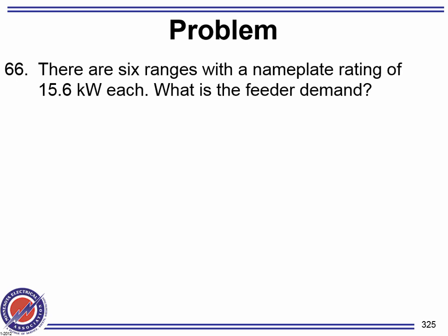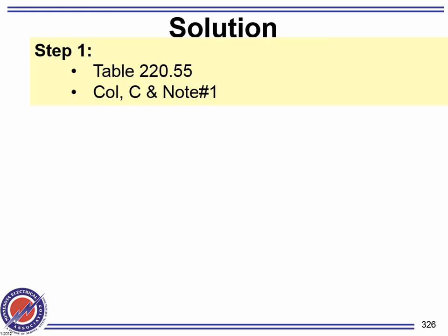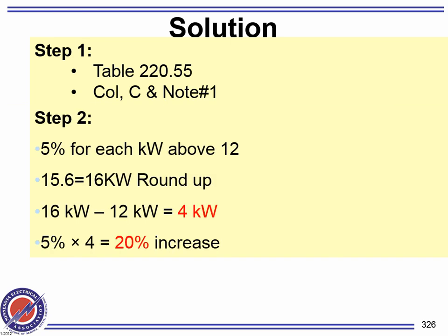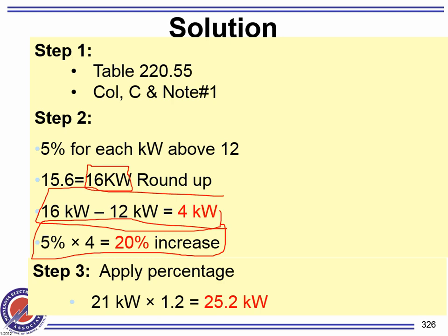Let's look at this one, where there are 6 ranges with a nameplate rating of 15.6 kW each. What is the feeder? So this is column C, note number 1. Is any one of them, guys, under A or B? No. So they're under C. They're 15.6, which rounds up to 16. How far is 16 from 12? 4. So for every kW increase, 5%. Then you increase your demand for 6 ranges by 1.2.